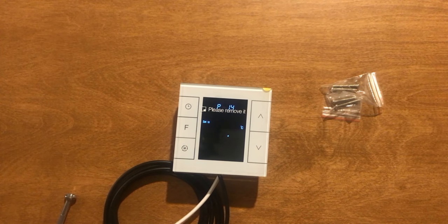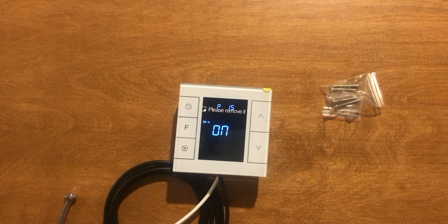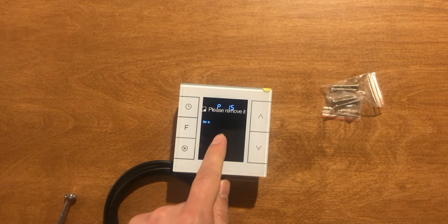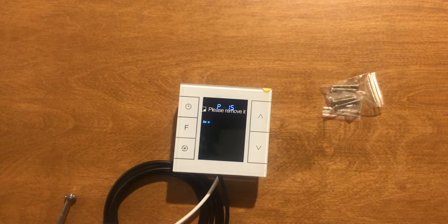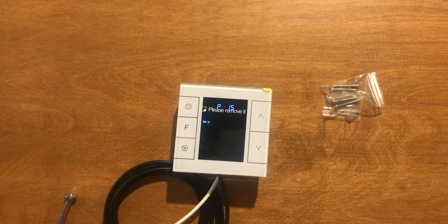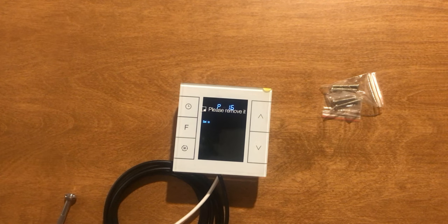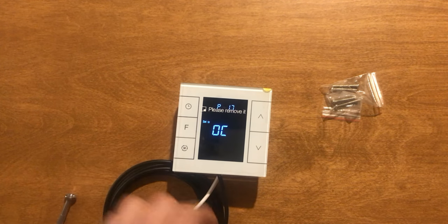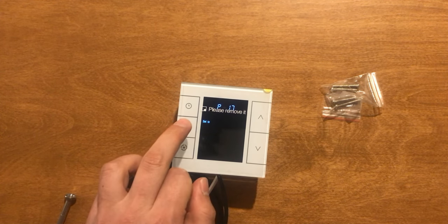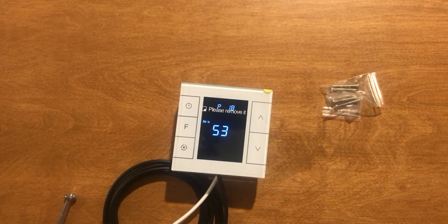P14 is outdoor temperature calibration. P15 is control based on external temperature. If we want to have the thermostat control based on external temperature, P15 must be turned on. P16 displays external temperature if it is on. P17 is temperature format, Fahrenheit or Centigrade, and P18 restores factory settings.